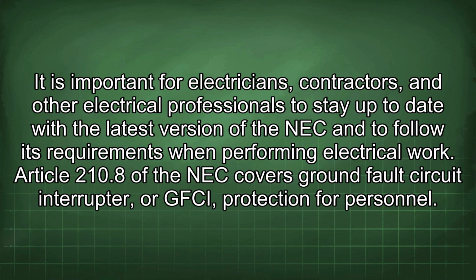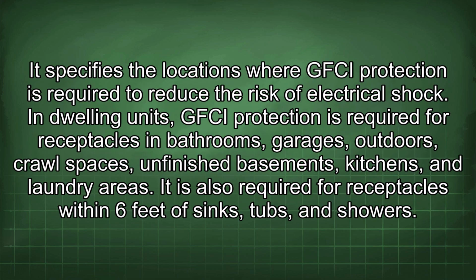Article 210.8 of the NEC covers ground fault circuit interrupter, or GFCI, protection for personnel. It specifies the locations where GFCI protection is required to reduce the risk of electrical shock. In dwelling units, GFCI protection is required for receptacles in bathrooms, garages, outdoors, crawl spaces, unfinished basements, kitchens, and laundry areas. It is also required for receptacles within 6 feet of sinks, tubs, and showers.